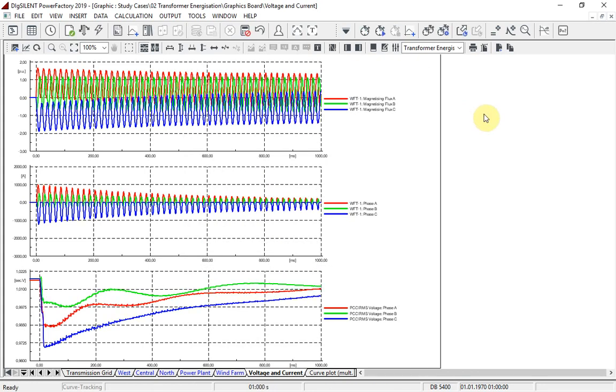The transformer is energized at T equals zero by closing the circuit breaker of all three phases. After closing the circuit breaker, the magnetic flux in the three phases exceeds 1 per unit, as shown here, and will drive the transformer into saturation.